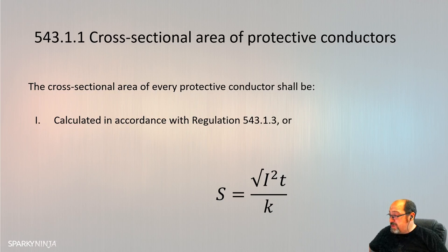which is one of the reasons why we're supposed to do PAT testing at 25 amp. We're supposed to actually challenge the protective conductor to break with PAT testing. So that's what we've done there: we've verified a protective conductor can tolerate the fault condition for the period of time that the fault condition will be there. Right, well, that was calculation.